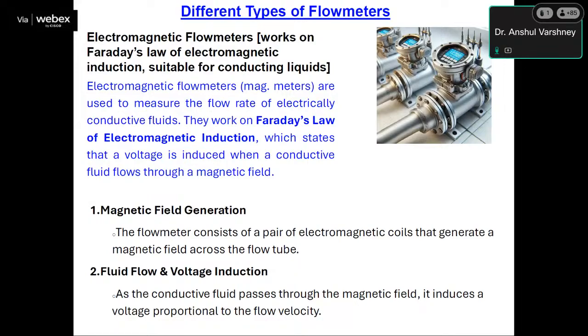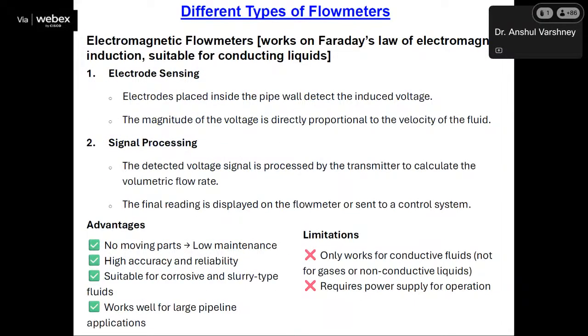There are various parts of this type of flow meter, like magnetic field generation. The flow meter consists of a pair of electromagnetic coils that generates a magnetic field across the flow tube. As the conductive fluid passes through the magnetic field, it induces a voltage proportional to the flow velocity. Next is electrode sensing. Electrodes placed inside the pipe detect the induced voltage, and the magnitude of that voltage is directly proportional to the velocity of the fluid. With that velocity, you can directly calculate the flow rate or totalized volume.